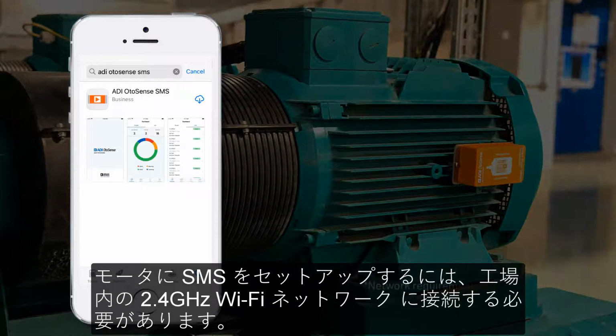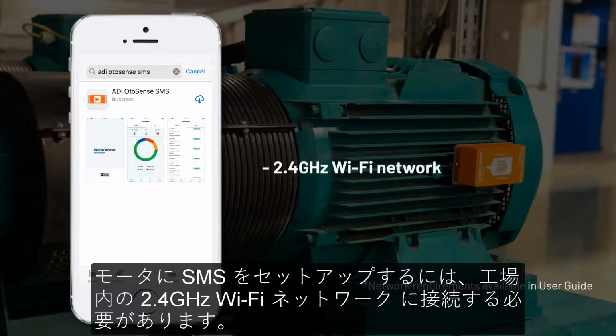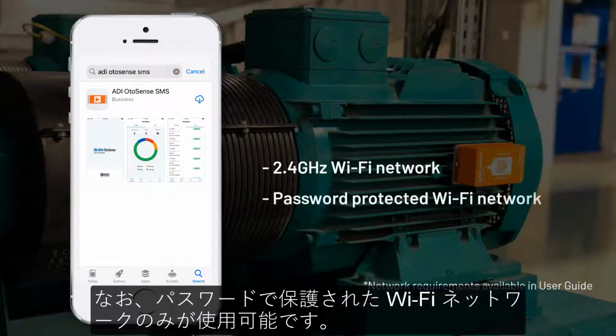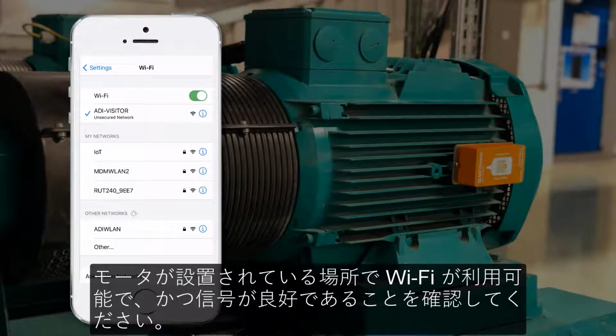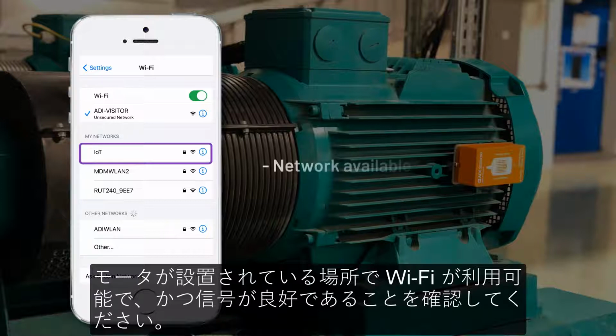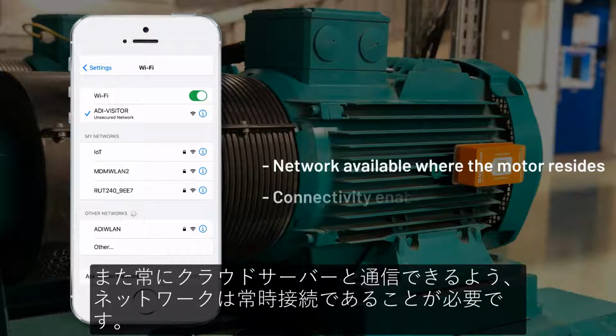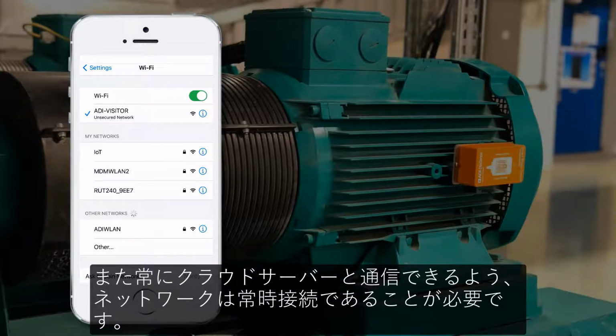To complete the setup of an SMS on a motor, you need to connect it to an existing 2.4 GHz Wi-Fi network in the plant. Note that only password-protected Wi-Fi networks can be used. Make sure you can see that the network is available in the Wi-Fi settings of your mobile device where the motor resides and that there is a good signal. This connectivity must be enabled 24/7 so the device can communicate with the cloud server at all times.